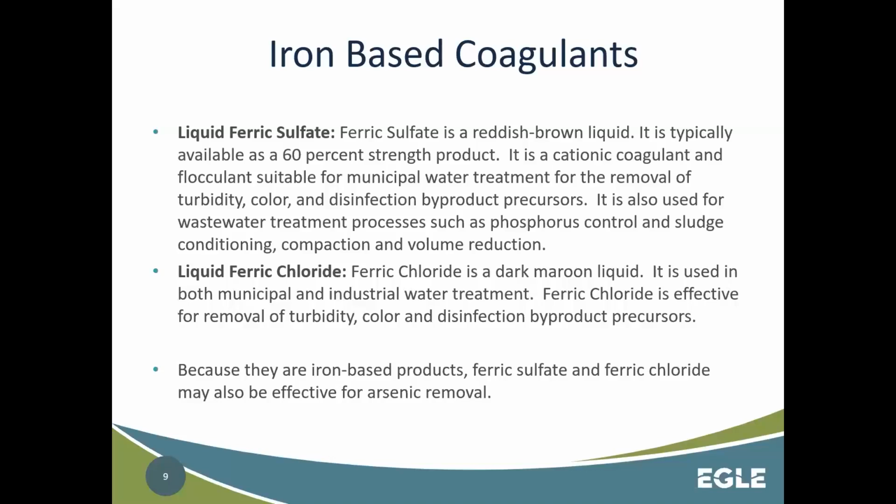Liquid ferric chloride is a dark maroon liquid. It is used in both municipal and industrial water treatment. Ferric chloride is effective for the removal of turbidity, color, and disinfection byproduct precursors. Because they are iron-based products, ferric sulfate and ferric chloride may also be effective for arsenic removal.